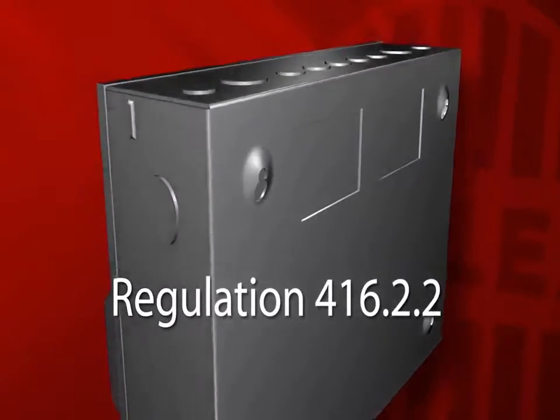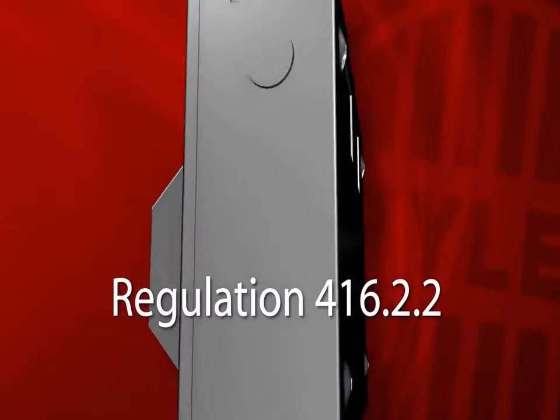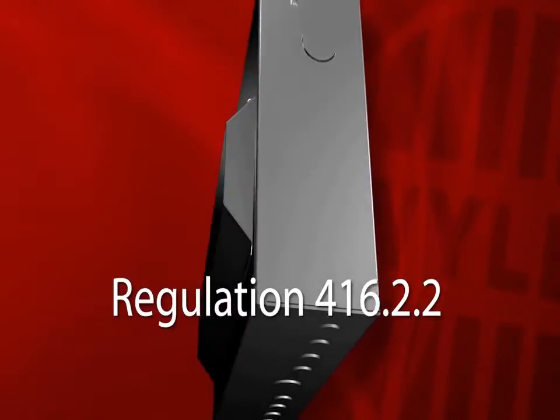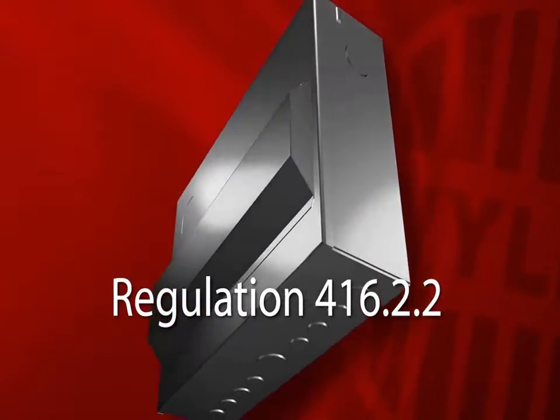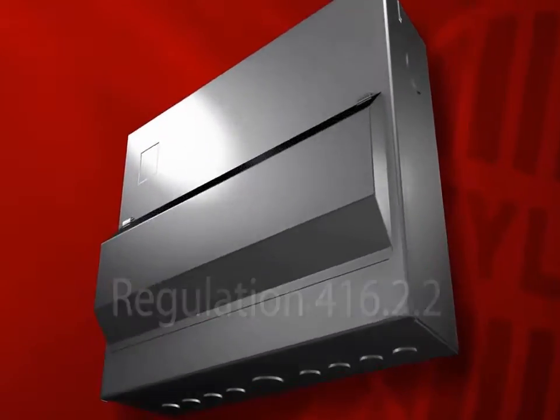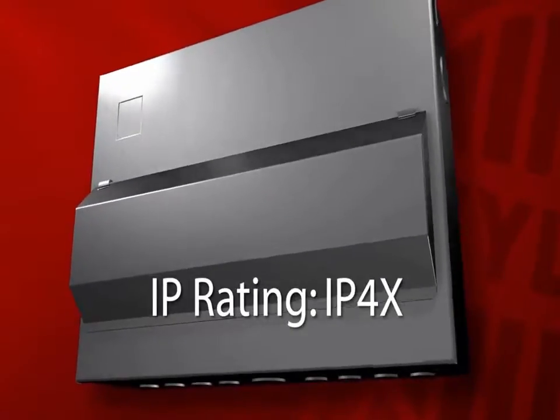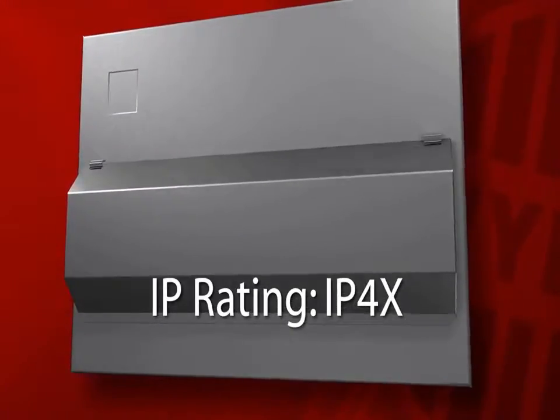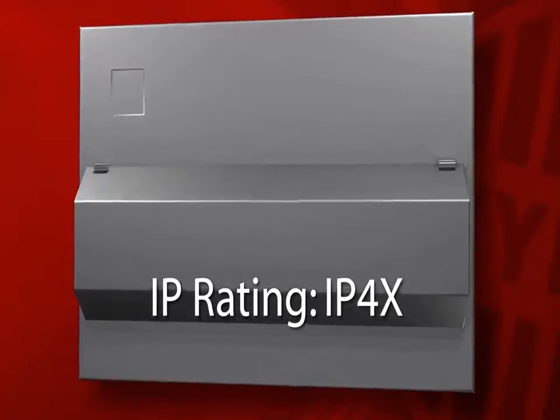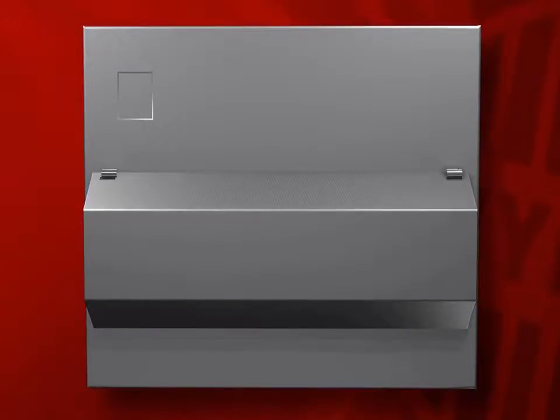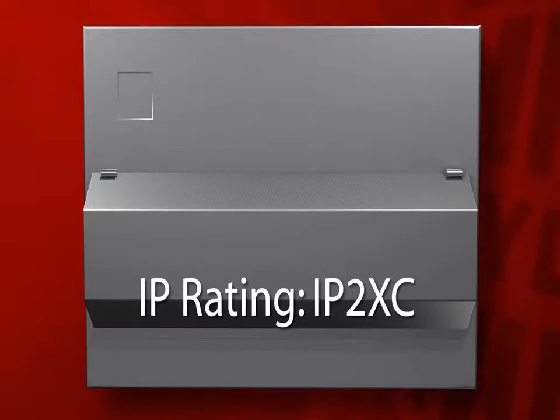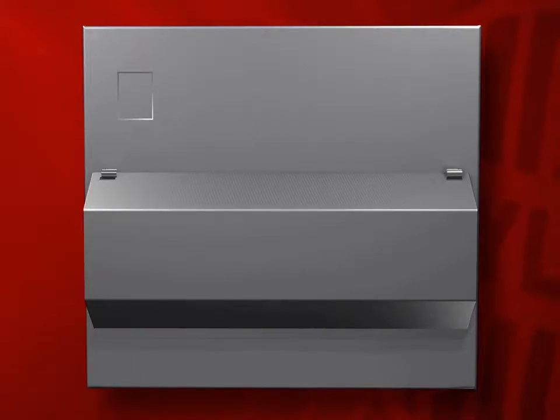Regulation 416.2.2 of the wiring regulations also requires the installer to ensure that the consumer unit, when fully installed, achieves an IP rating of IP4X on the top elevation, if this is readily accessible, and elsewhere on the consumer unit, the other elevations of the enclosure must be to IP2XC. This can be achieved in many ways. The following are examples of methods that may be used, including the use of a mains tails gland.